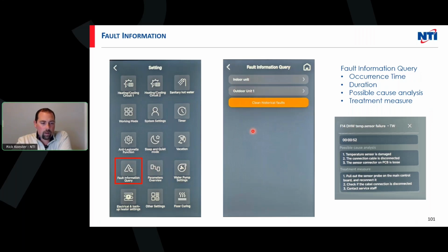But if we were to click on an error, and I created this one in our lab in New Bedford for you guys, I created this error by basically not having an indirect sensor there, but telling the machine that it was going to do domestic hot water, and it gave me a temp sensor failure. It'll give me the time and date. It'll tell you how long the error was present, because some errors may pop up and fix themselves, and then you don't know they're there until you go back into the history and take a look at it. But it's going to give me some possible cause measures to follow.